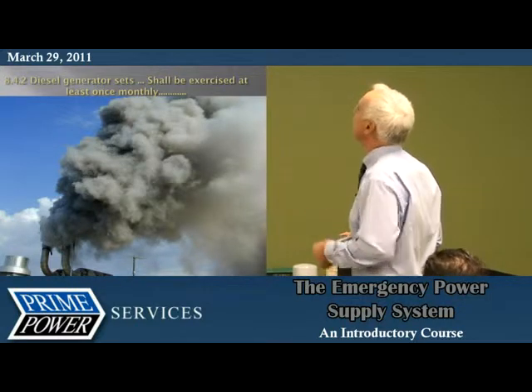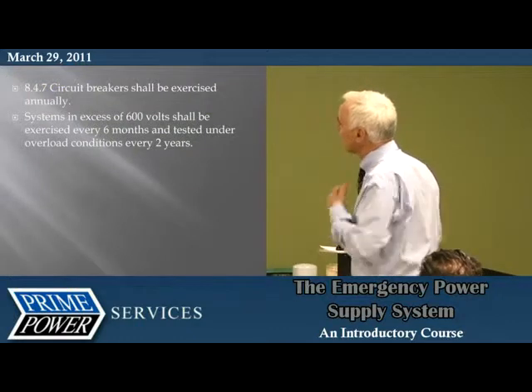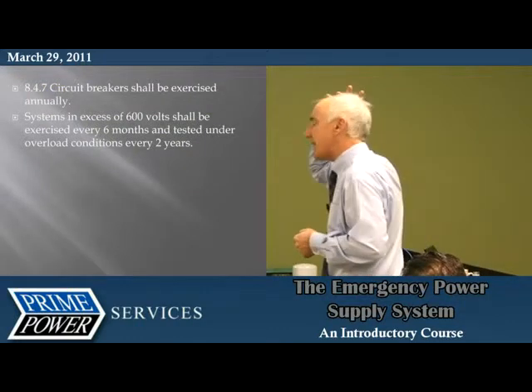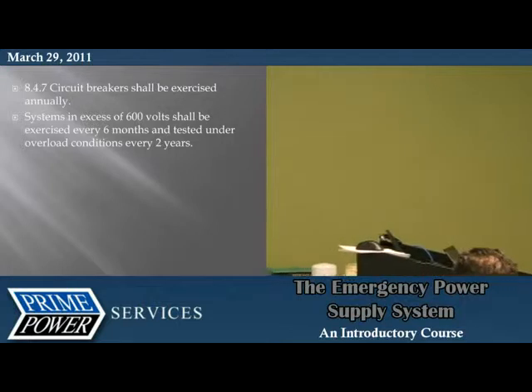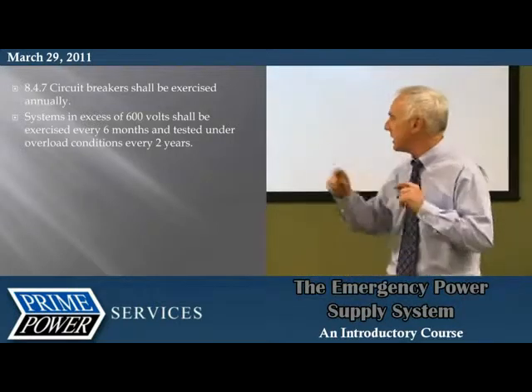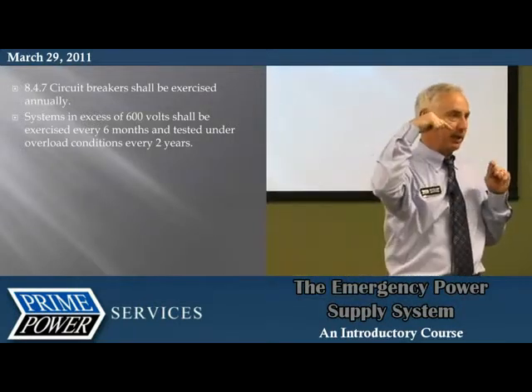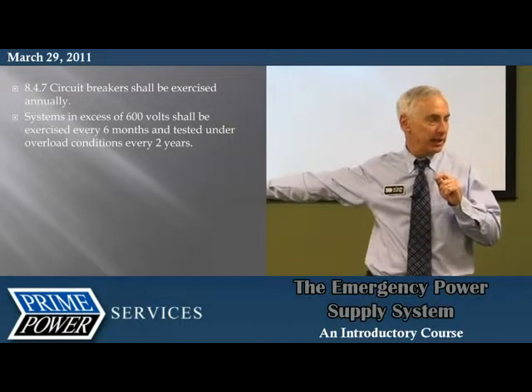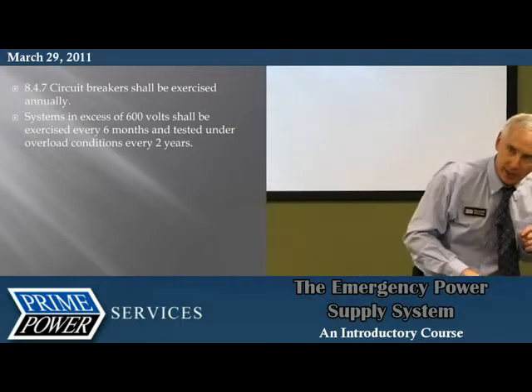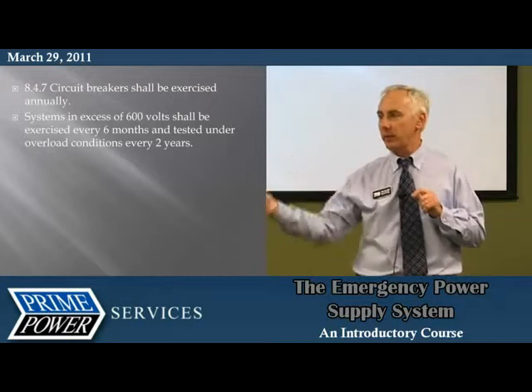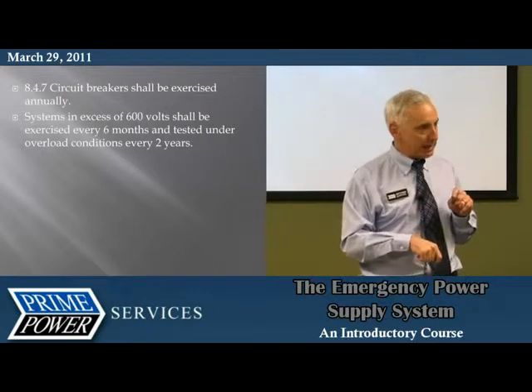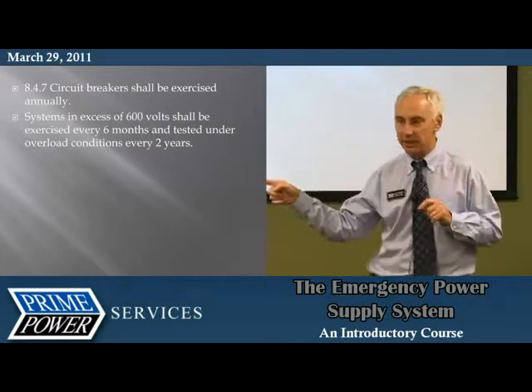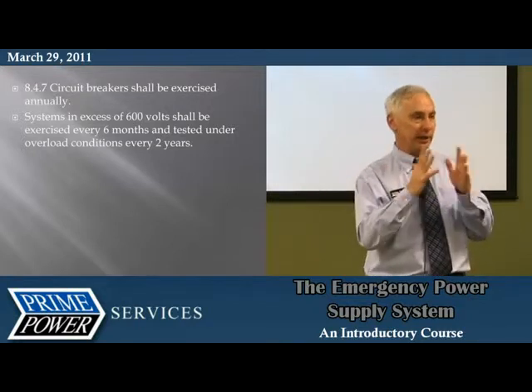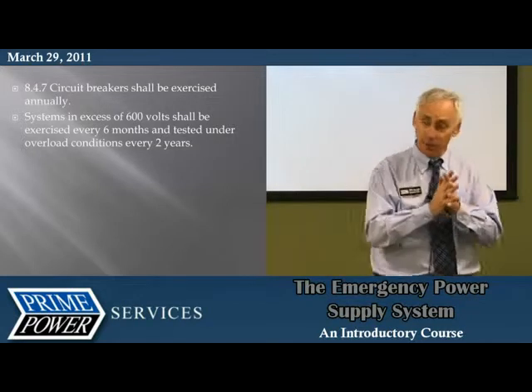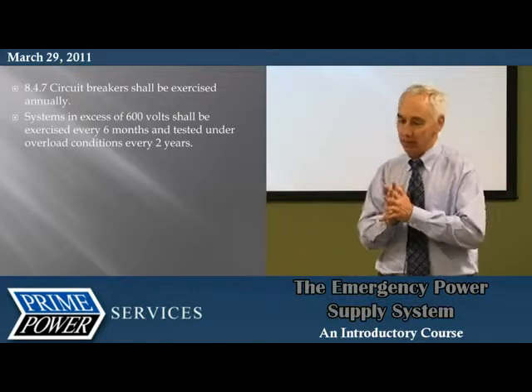Okay, circuit breakers shall be exercised annually. Specifically, this is talking about any circuit breaker that is in line from the emergency generator into the system. And exercised in this particular case really only means we have to open it and close it. And why is that? The same reason we have to exercise that transfer switch, we're trying to open and close and clean our contacts. We want to be sure that breaker can open and close.